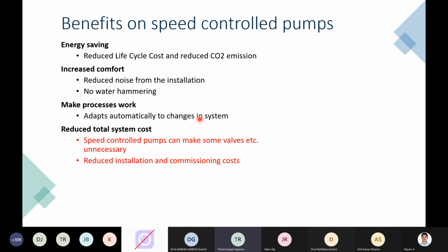Speed control pumps can make some valves unnecessary, because you can avoid a valve at your discharge since you are not going to throttle the discharge. The VFD is going to take care of the pump speed fluctuation. It also reduces installation and commissioning costs, because in some cases the installation of multiple things can be avoided, and having a single entity with pump, motor, VFD, and controller makes more sense and is more energy efficient also.